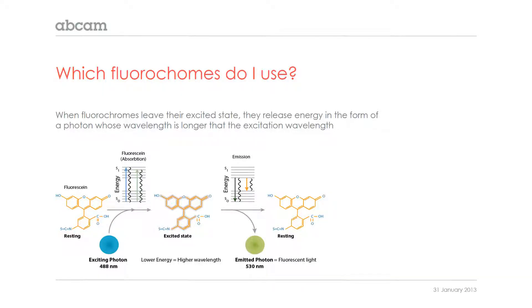Fluorochromes all basically work on the same principle in that we excite the fluorochrome by a laser, and this laser should be roughly in the area of the maximum extinction coefficient of the fluorochrome. Once the electron goes into the higher orbital, which is quite unstable, it will then go back to the stable orbital. Within this process, there's a certain amount of heat dissipated, and this is consequential in that the excitation wavelength and the emission wavelength of the photon falling back down to the more stable configuration will always be a longer wavelength than the excitation.